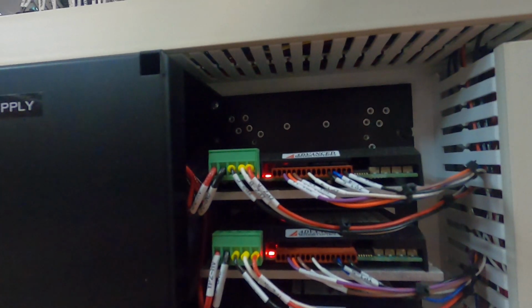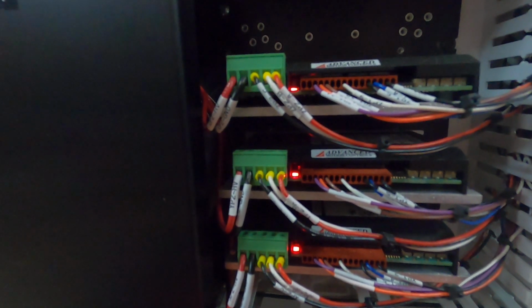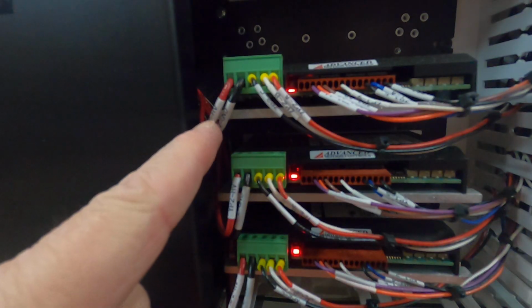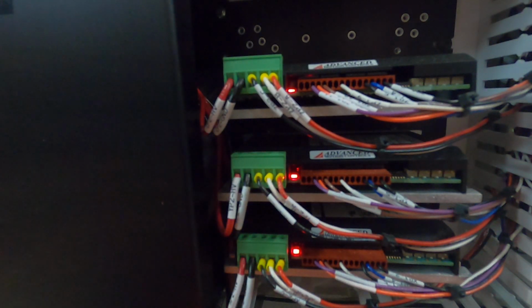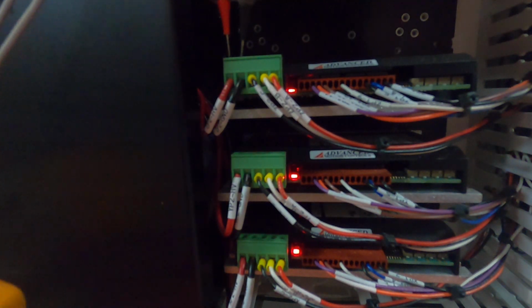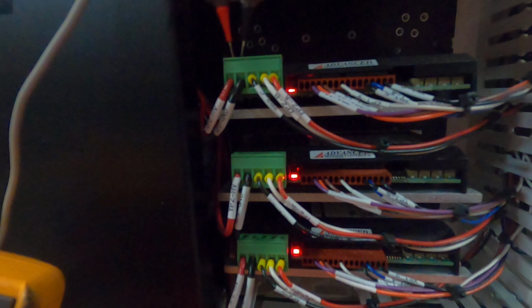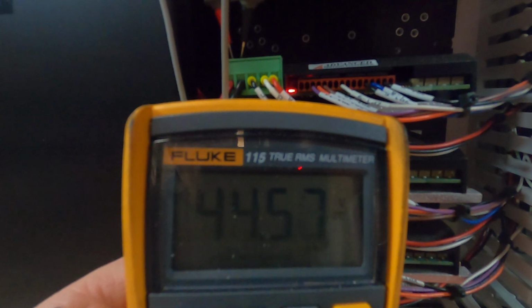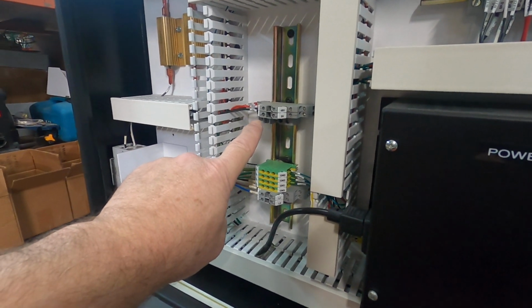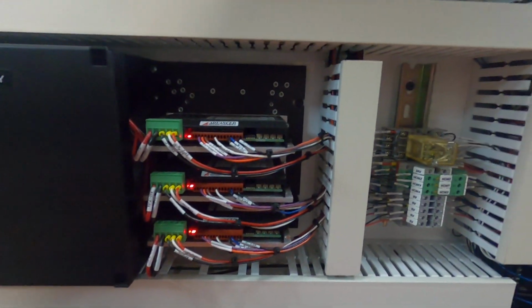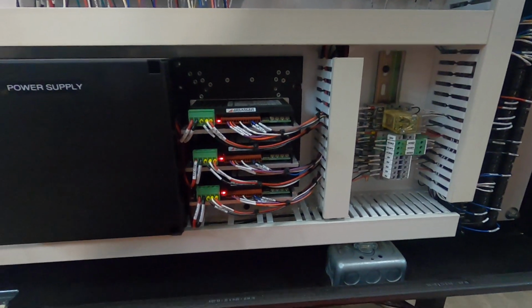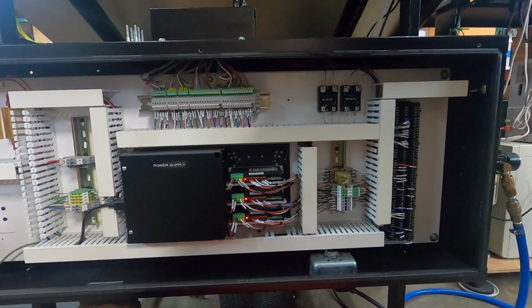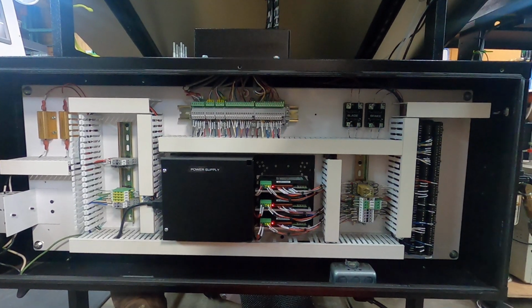You can see that this has got lights on it. These drives, each one of these drives. And you can see like this signal says HV and this one says ground. So this is DC voltage. So if I put my black probe on the screw where the black wire goes, and I put my red probe on the screw where the red wire goes, get over there, I've got 44 volts, same as I had over here, because those are all tied together. Okay, so that's how you can check the voltage in your system to make sure you've got the right voltages where you're supposed to have them. Okay.